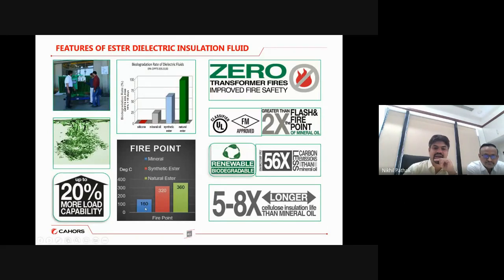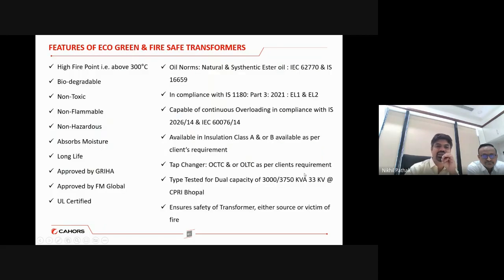So here you can see the mineral oil is having a 160-degree fire point, and the natural ester oil is having 360-degree as a fire point. So it is completely biodegradable. So these are the features. Again, the oil has a fire point of 300-degree. It is biodegradable, non-toxic, non-inflammable, non-hazardous, and it helps to absorb the moisture from the transformer. And it is approved by GRIHA also, Green Habitat Government of India. So GRIHA is the body for certifying the green certifications of the different products.